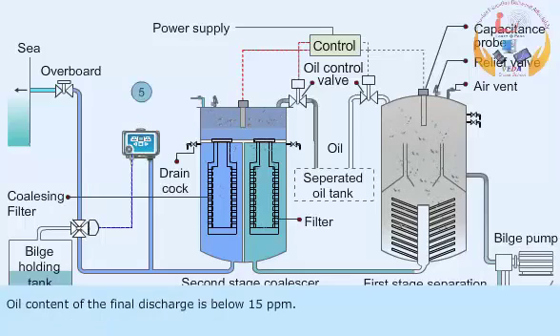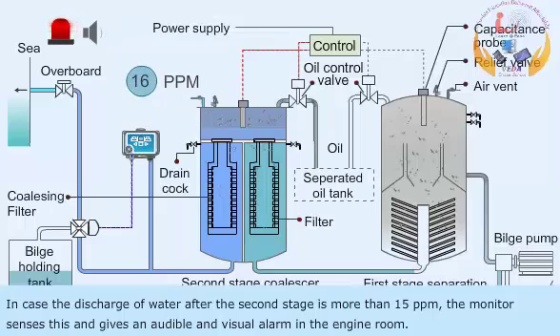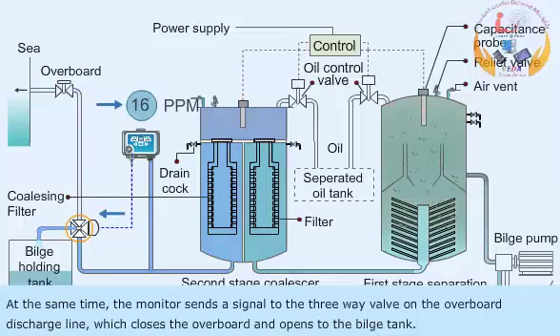The oil content of the final discharge is below 15 ppm. In case the discharge of water after the second stage is more than 15 ppm, the monitor senses this and gives an audible and visual alarm in the engine room. At the same time, the monitor sends a signal to the three-way valve on the overboard discharge line, which closes the overboard and opens to the bilge tank.